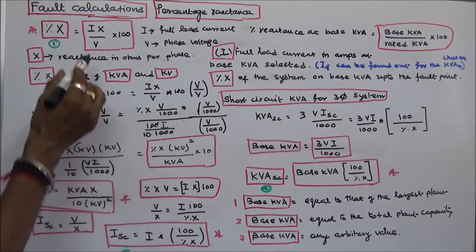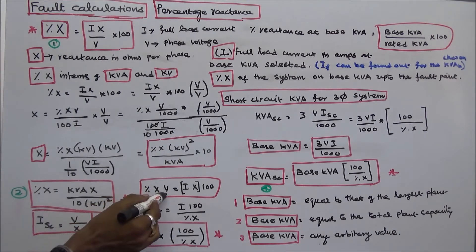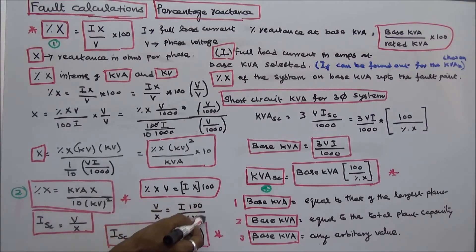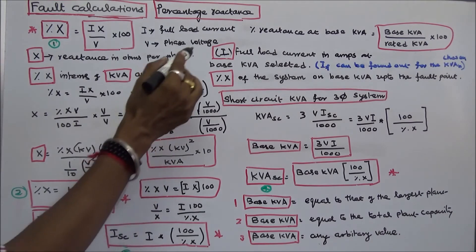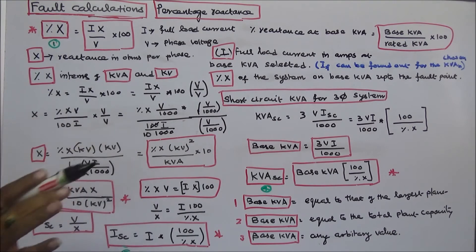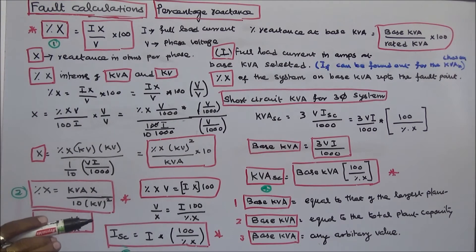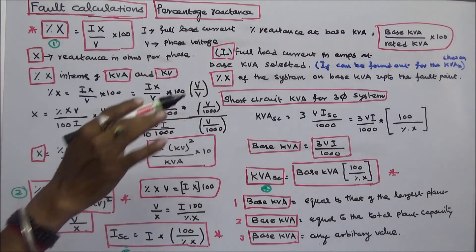From the percentage X formula: percentage X times V equals I times X times 100, so V divided by X equals I times 100 divided by percentage X. Therefore, short circuit current ISC equals I times 100 divided by percentage X, where I is the full load current in amps at the base KVA selected.